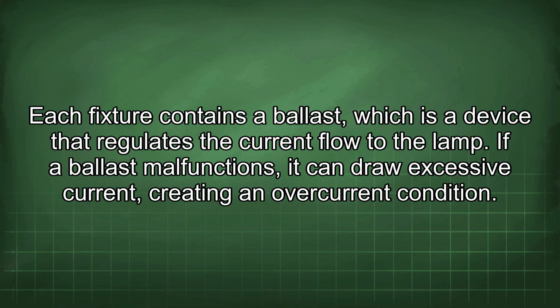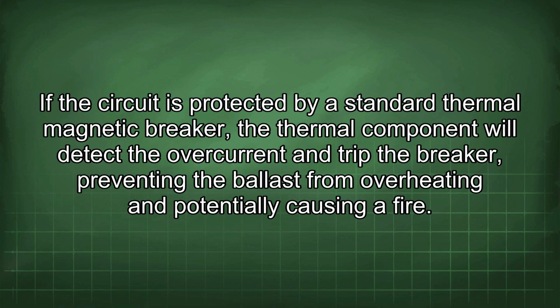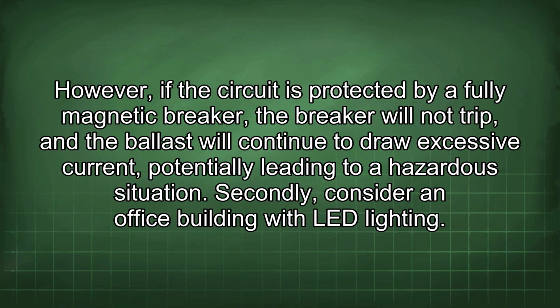If a ballast malfunctions, it can draw excessive current, creating an overcurrent condition. If the circuit is protected by a standard thermal magnetic breaker, the thermal component will detect the overcurrent and trip the breaker, preventing the ballast from overheating and potentially causing a fire. However, if the circuit is protected by a fully magnetic breaker, the breaker will not trip, and the ballast will continue to draw excessive current, potentially leading to a hazardous situation.